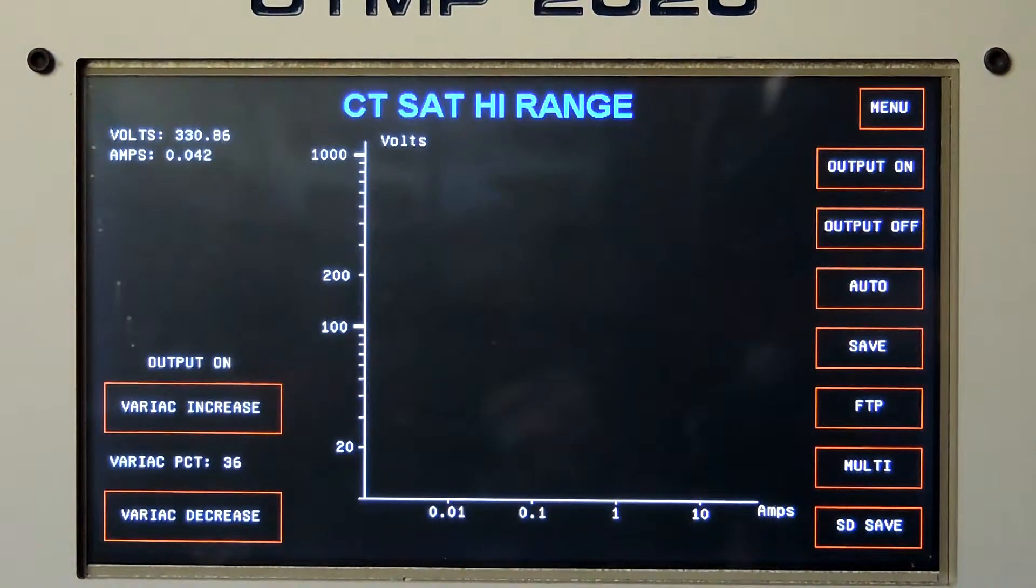As it proceeds through all the tests, it's now raising the voltage and taking voltage and current data. It has reached the saturation point, that's why it says 'sat' under amps. You may be able to hear the CT humming there.